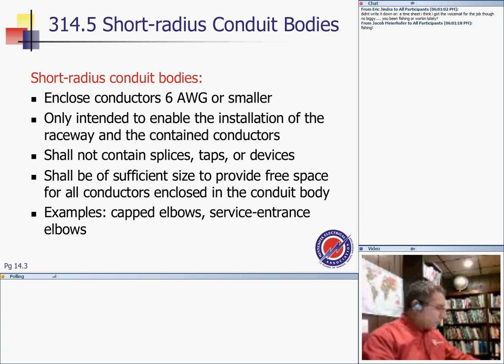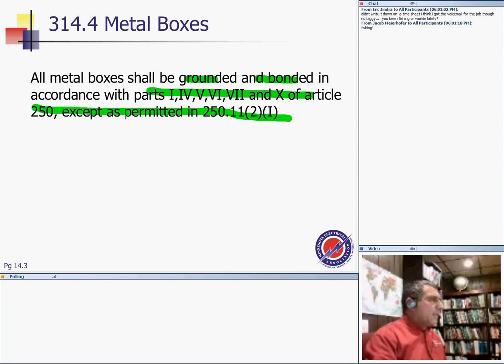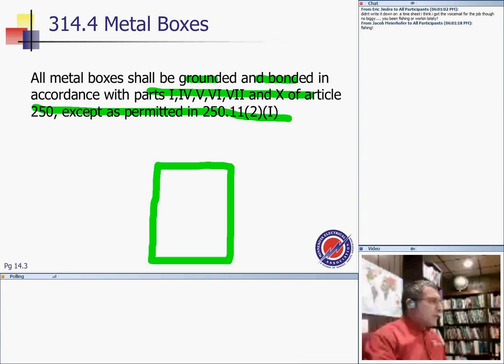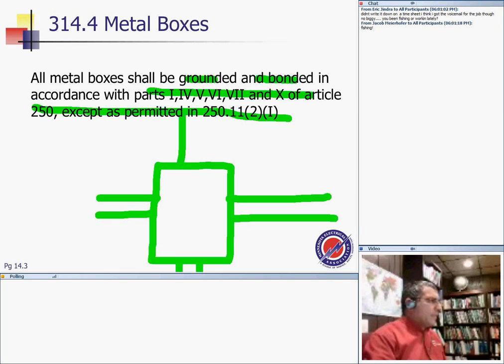Sometimes you have to use a type of conductor for bonding and grounding. And I'm not going to get into special boxes, pull boxes, and how you ground and bond them. A conduit coming in with a set of connectors from this side, another conduit coming from this side, and a conduit coming from this side. This is like a J box, not a J box, a pull box. So you might have to bond, and these are not threaded, just a set screw.